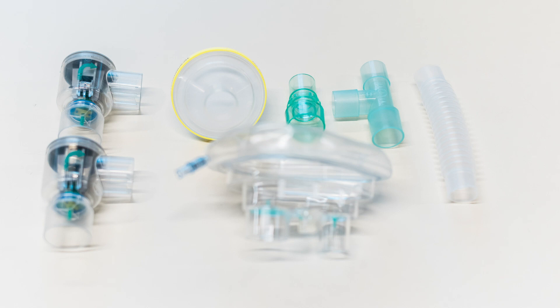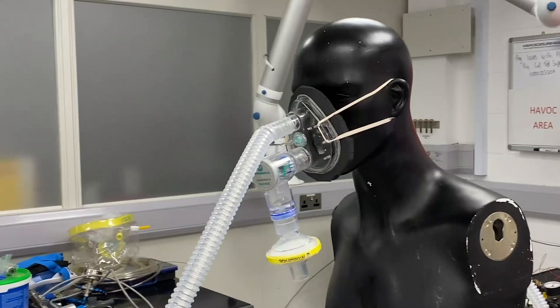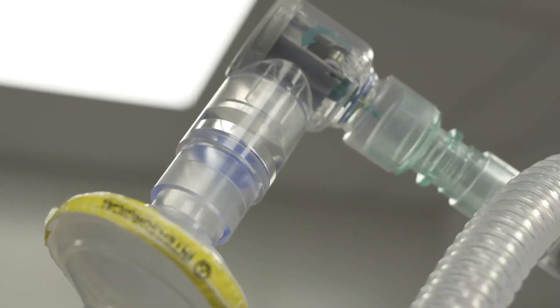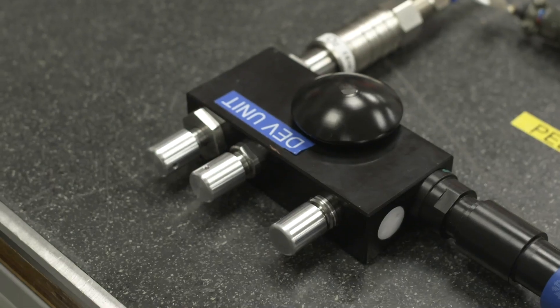One of the advantages of these CPAPs is that treatment usually takes around three to four days, and it's also in general a lot easier to train healthcare workers to use the devices. So we went back to a historic device called the Respironics Whisperflow, which is an off-patent device that had been used very widely in the UK up to around 15 years ago.